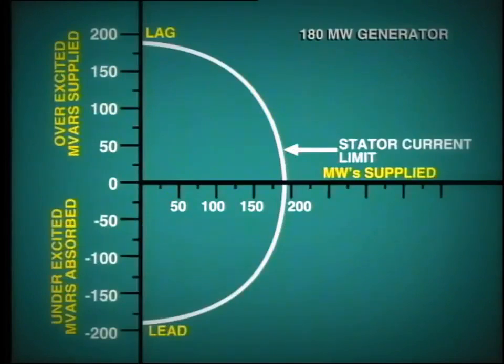This generator capability curve shows us the limitation on MVA due to current in the stator. For example, at this megavar loading, we can only produce this amount of active power to stay within the machine's capability.